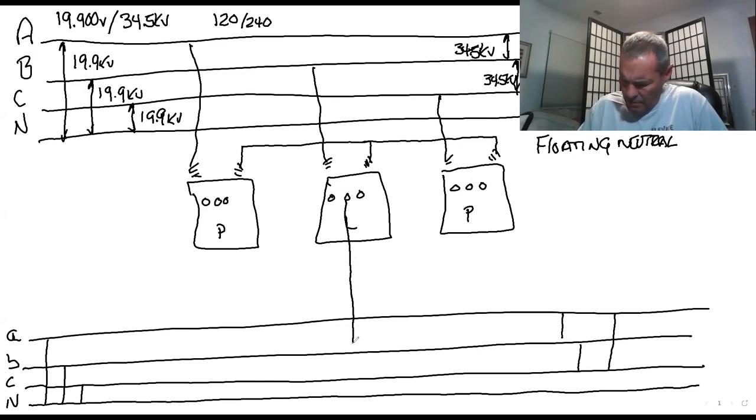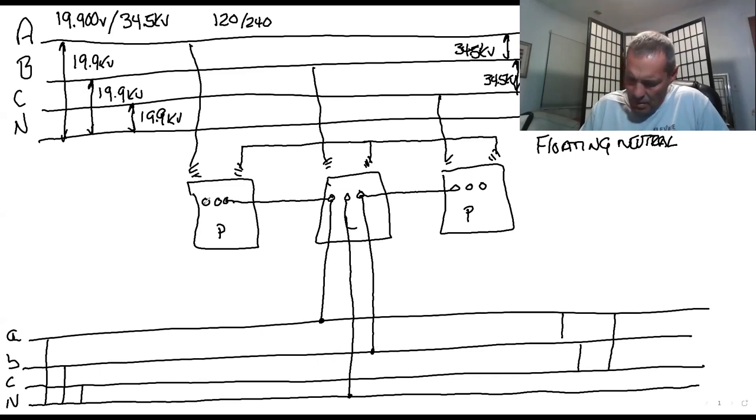Now here's where I deviate a little bit and you'll notice the difference in the two. Always draw your neutral line in first. I'll do it just like open delta. A, B. I'm going to tie the transformers together, bang, bang, and you'll notice it's the two closest bushings together, here, here, here, and here. Then I only have one line remaining. I've got A and B covered, correct? Power goes down to C. And the line here at the bottom that interconnects them both is really what's tying them both together.